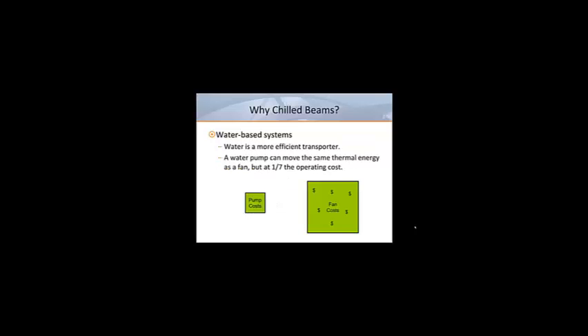It also takes far less energy to move water through a pipe than it does to move air through a duct. Since the distance is the same, the potential savings are huge. A water pump can move the same amount of thermal energy as a fan, but at one-seventh the operating cost.